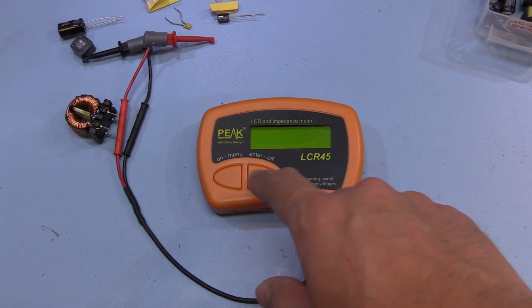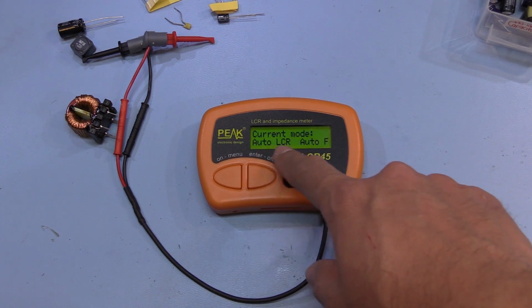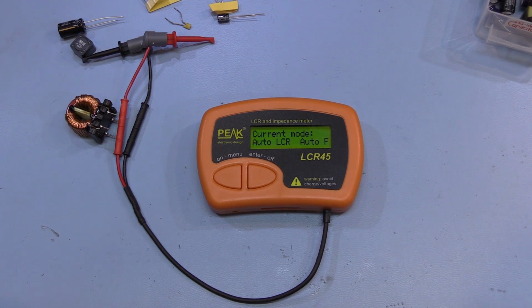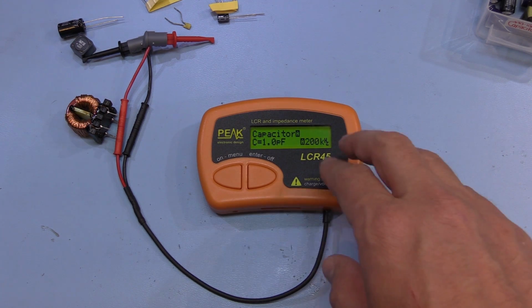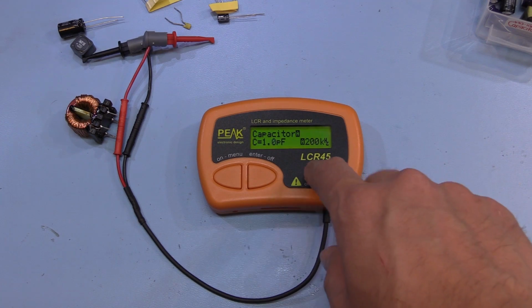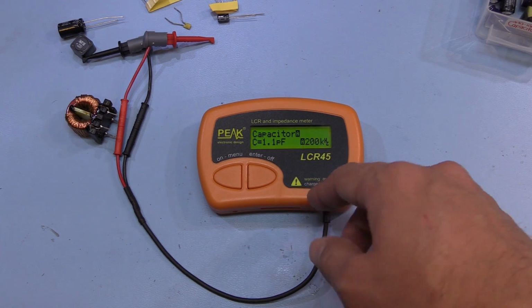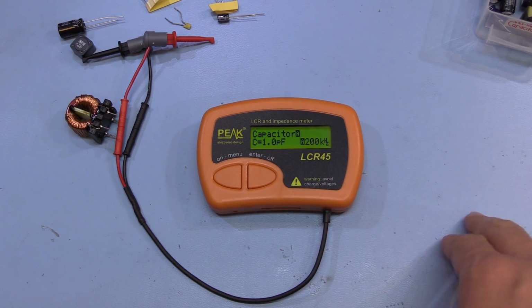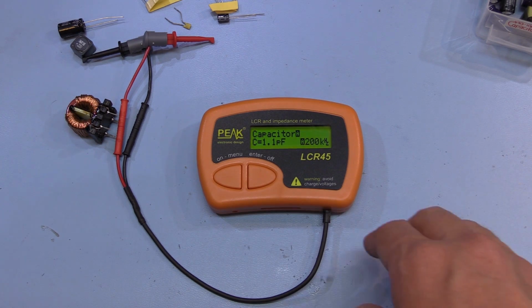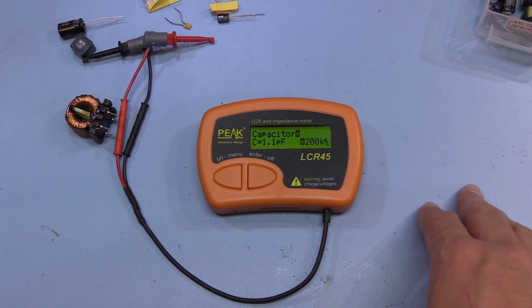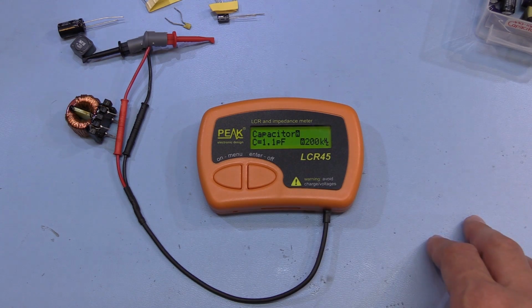so then you can set it into a manual ranging mode. But if we turn on the device, you will notice that it did actually say calibration due 2016, so there are clearly some components in here which may drift with age, so if you want to keep it on specification you do need to send it back for calibration, although just for indication purposes most of the time this is going to be accurate.